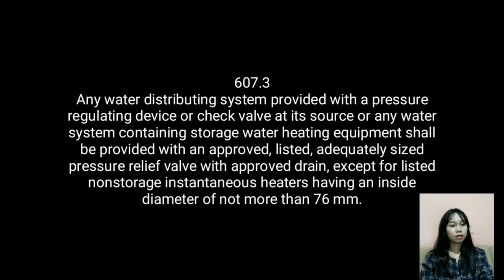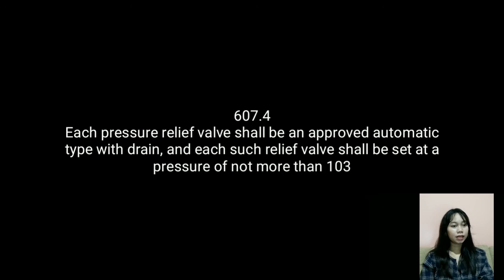In addition to the required pressure relief valve, an approved and listed expansion tank or other device designed for intermittent operation for thermal expansion control shall be installed whenever the building supply pressure is greater than the required relief valve pressure setting, or when any device is installed that prevents pressure relief through the building water supply. The tank or device shall be sized in accordance with the manufacturer's recommendations.